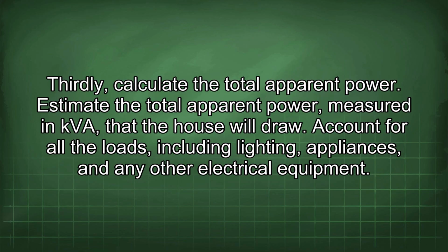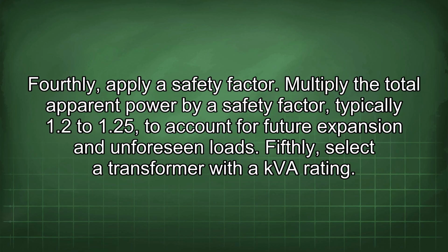Thirdly, calculate the total apparent power. Estimate the total apparent power, measured in kVA, that the house will draw. Account for all the loads, including lighting, appliances, and any other electrical equipment. Fourthly, apply a safety factor. Multiply the total apparent power by a safety factor, typically 1.2 to 1.25, to account for future expansion and unforeseen loads.